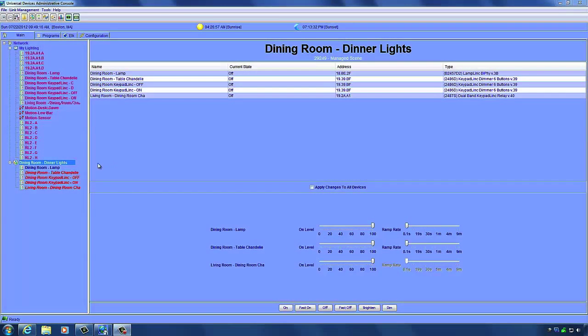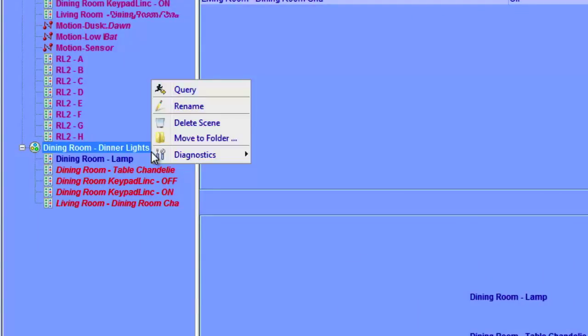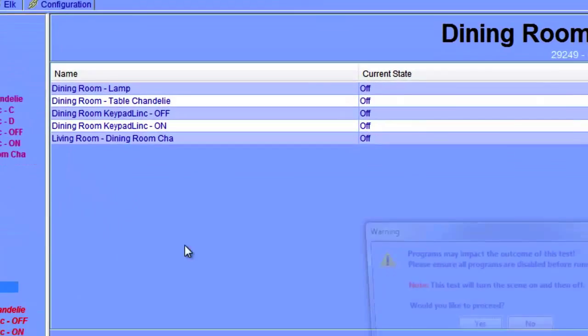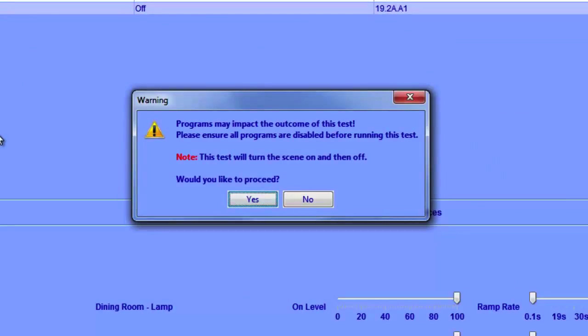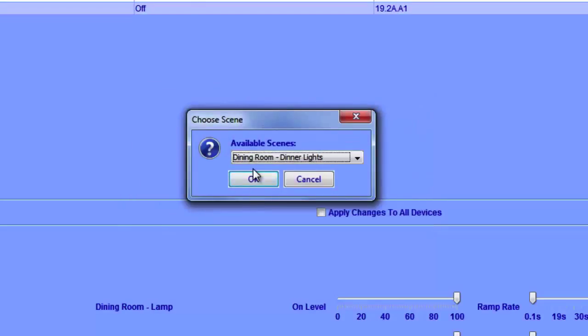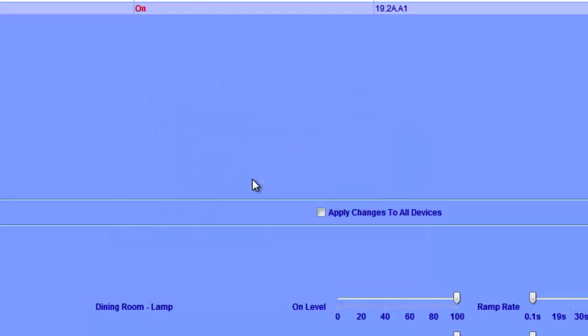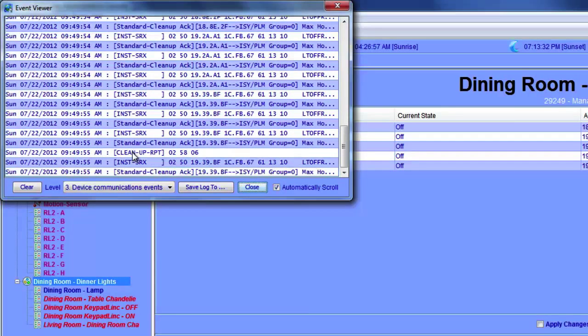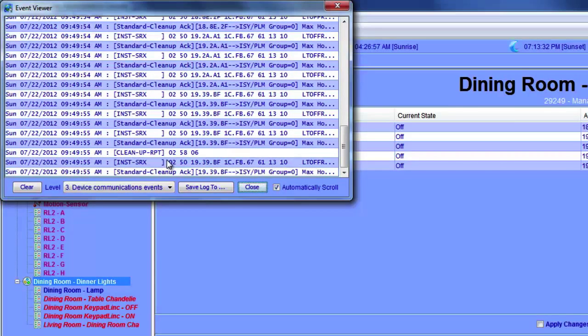Yet another diagnostic tool is the Scene Test. Access it by right-clicking on the scene, going to Diagnostics, Scene Test — or via Tools, Diagnostic, Scene Test. This will turn the scene on and then off, and you'll be able to see the inst-srx responses in the diagnostic window. You should disable any programs associated with the scene first. Choose the scene you want to test. As you can see, the scene turned on and we see the results right in the window — everything was successful.